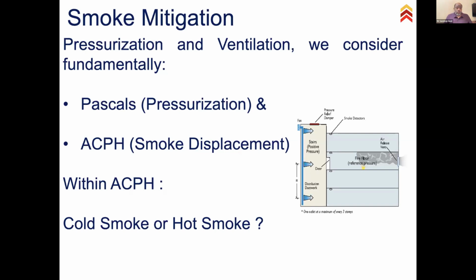In a kitchen, at home or at hotels, you put an exhaust chimney. Air comes from outside, picks up the fumes from cooking, and goes into the exhaust system to be thrown out. So ACPH, air changes per hour, is used in our normal lives without us knowing. Most of us as engineers know of it, but your family wouldn't know. We are silent users of ACPH in our businesses and lives, for dilution and controlling growth of nuisance relating to smell within the space - not smoke. So here you've got Pascals and ACPH, two different things, clear.